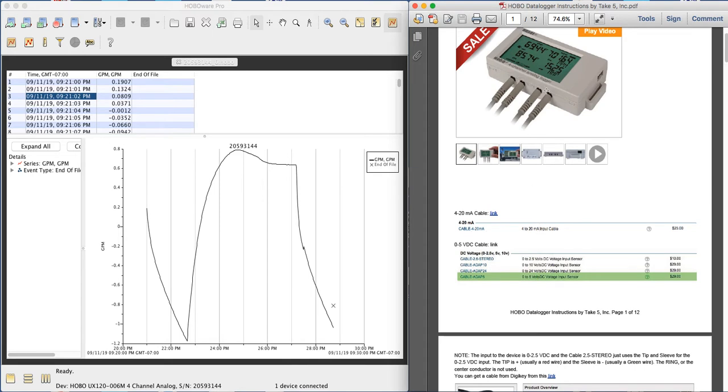These inputs are 0 to 2.5 volts DC. There are 4 channels. If you burn one of them up, use the others. We're going to light up channel 4 only, just for the purpose of collecting 4 to 20 milliamps. That means 0 to 10 gallons per minute.